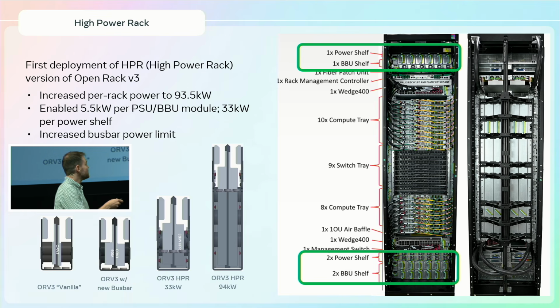Looking here, this is the back of the rack itself. You can see within the middle of the rack, vertically, that bus bar that connects all the power supplies to the IT shelves in a single power domain. You can also see the cable backplane cartridges, where all the cables supporting the NVLink scale-up domain are. We also have these large black reinforcements, which push back on the IT servers against that 6,000 pounds of force John mentioned earlier, to prevent things from blowing out the back of the rack.